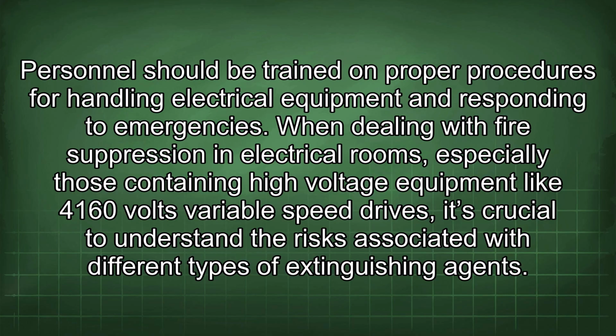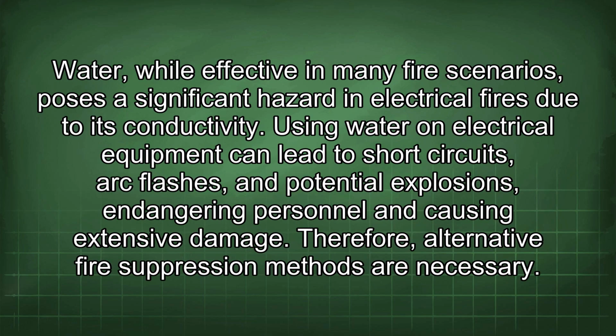When dealing with fire suppression in electrical rooms, especially those containing high voltage equipment like 4160 volt variable speed drives, it's crucial to understand the risks associated with different types of extinguishing agents. Water, while effective in many fire scenarios, poses a significant hazard in electrical fires due to its conductivity. Using water on electrical equipment can lead to short circuits, arc flashes, and potential explosions, endangering personnel and causing extensive damage. Therefore, alternative fire suppression methods are necessary.